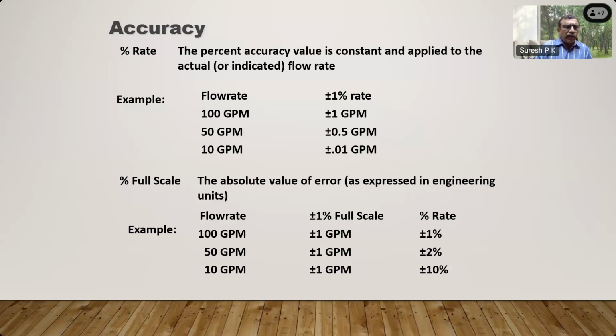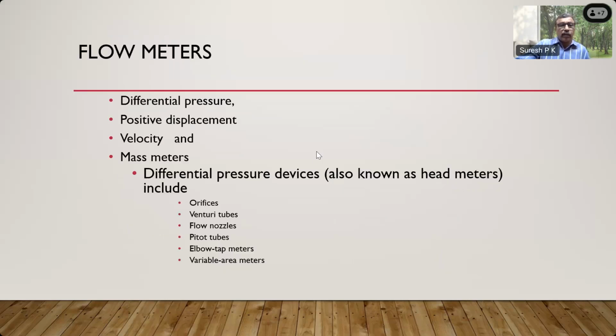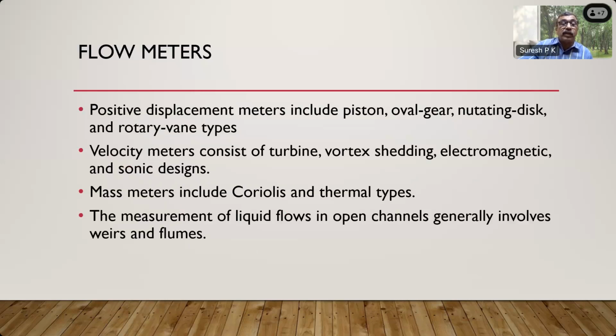Generally, I think reliable people don't go in for such misleading terms. Percentage of rate and percentage of full scale is something which has to be taken care of. I have given a general introduction to flow metering and the intricacies involved, the calibration intricacies involved. Now I will try to cover certain important flow meters which are used for flow measurement, like differential pressure, positive displacement, some velocity meters, and some mass flow meters.